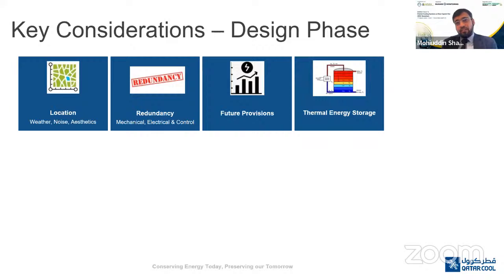The other aspect is the thermal energy storage systems. It is vital to have thermal energy storage on any district cooling plant, especially when you are in the range of around 10,000 TR, where it makes more economical sense. The energy storage could be water or ice. Water turns out to be the cheaper and most cost-effective option. Most of our plants have thermal energy storage, barring IDCP. It helps in shaving off the peak loads.